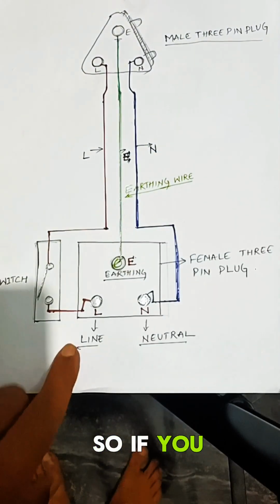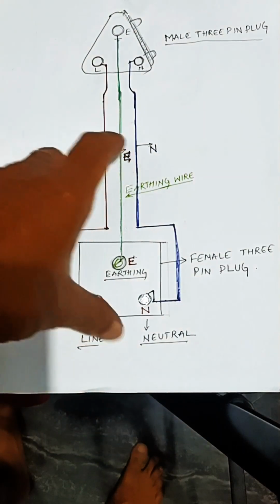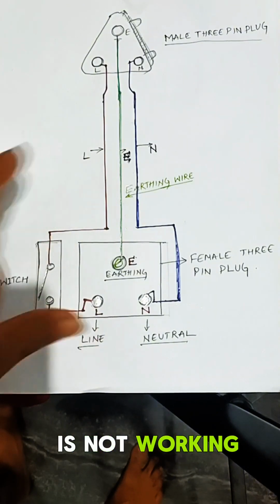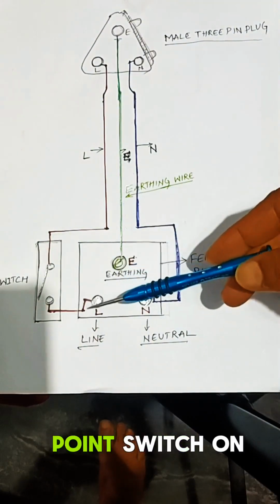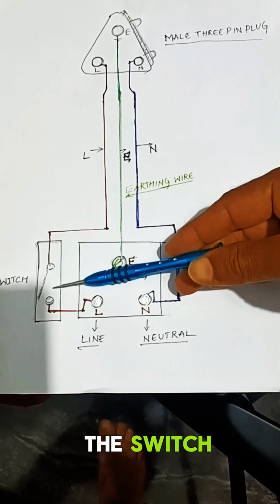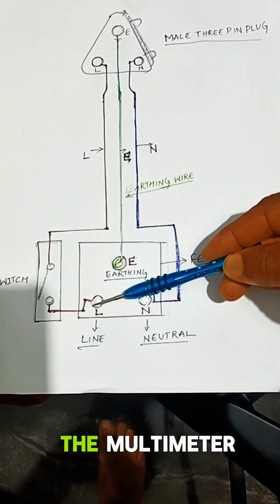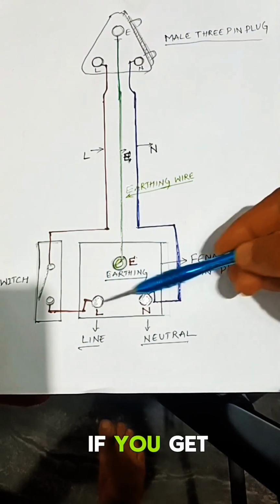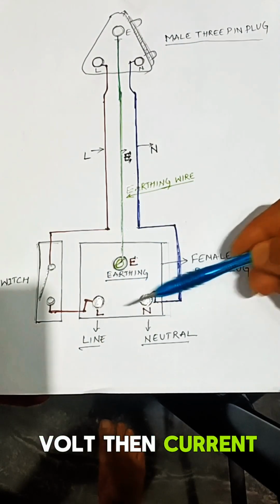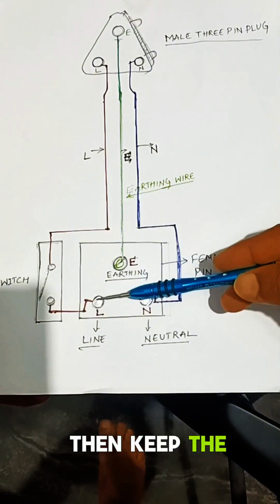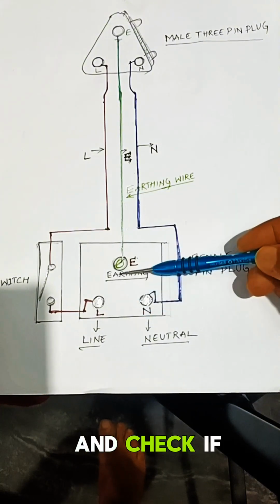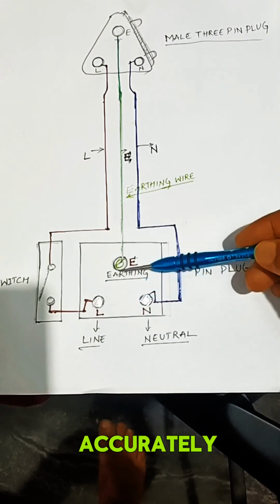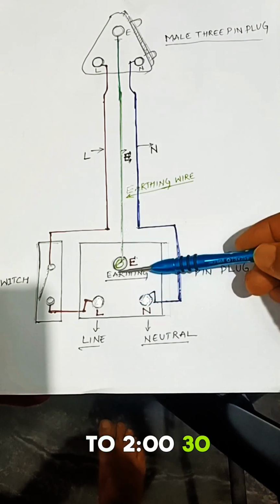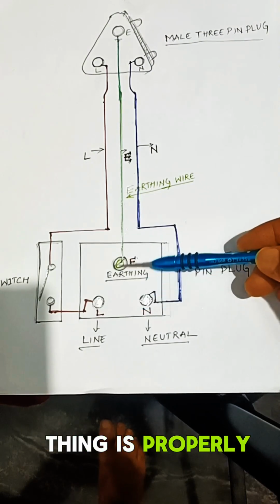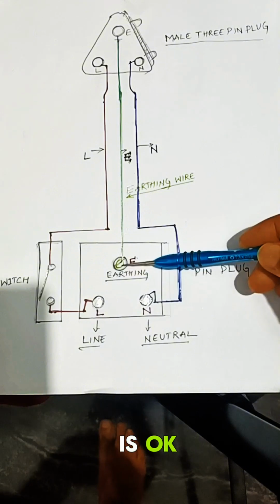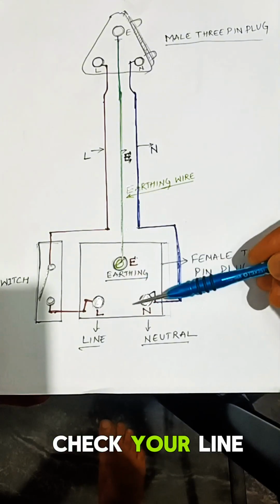So if you have a faulty extension board and it is not working, check these points. Switch on the switch, check with the multimeter, line and neutral. If you get 230 volts, then current is flowing. Then keep the probe in line and earthing and check. If the voltage is nearly 230 volts, then your earthing is okay. So this is how you can check your line wire.